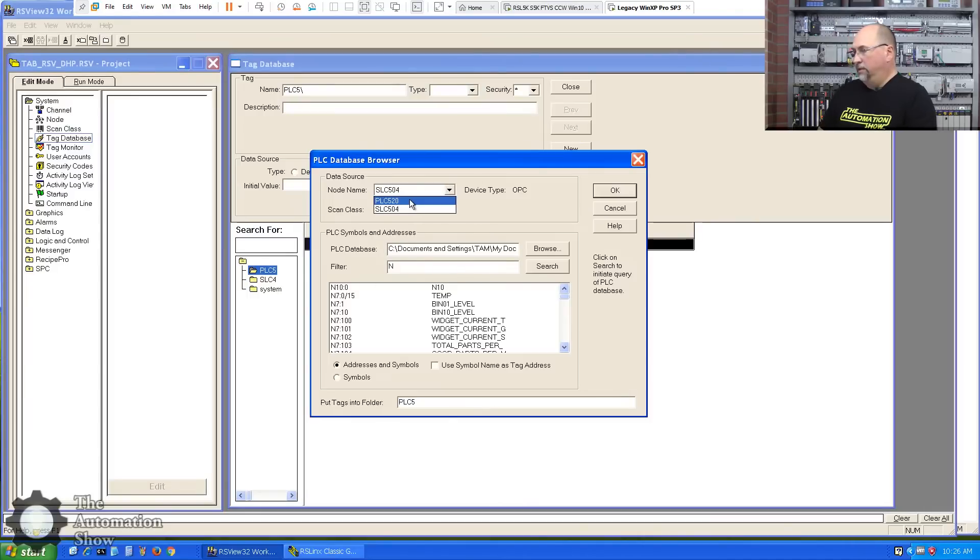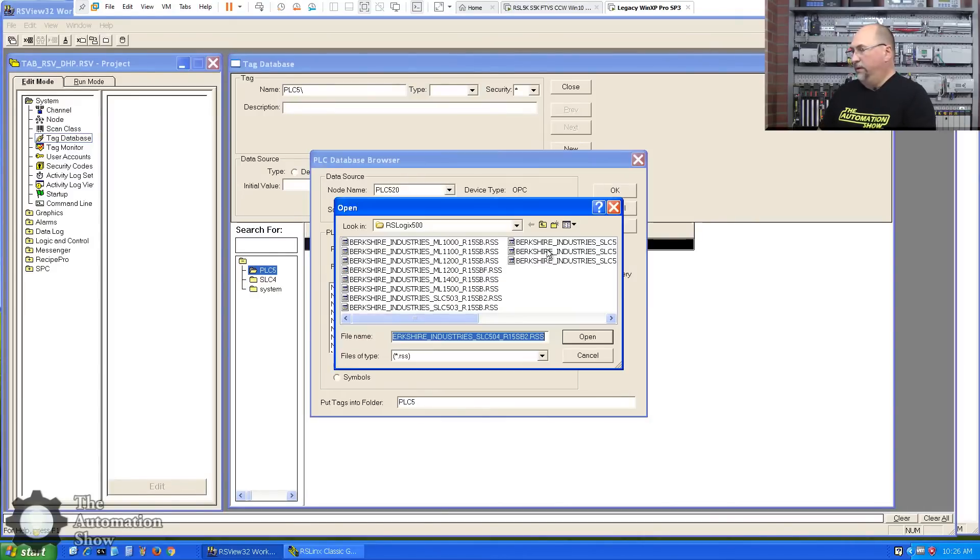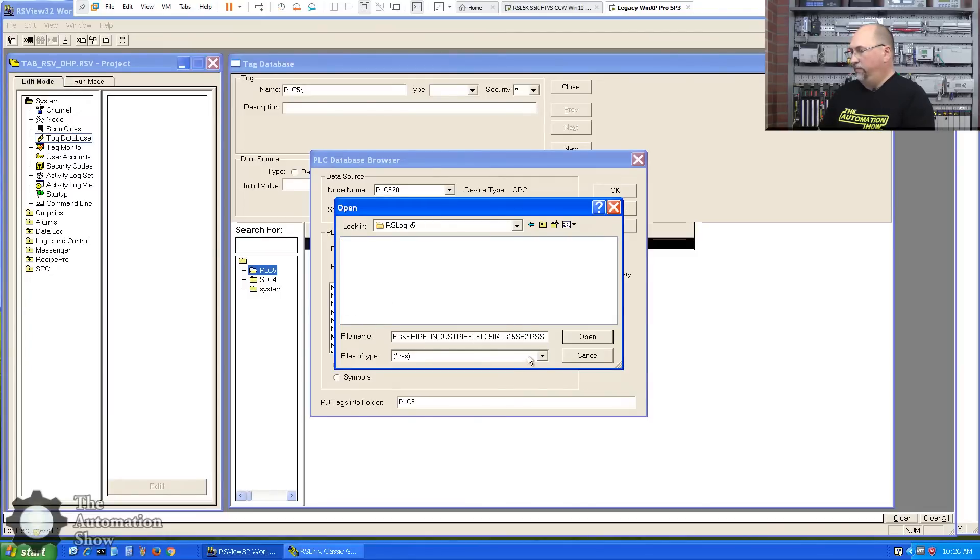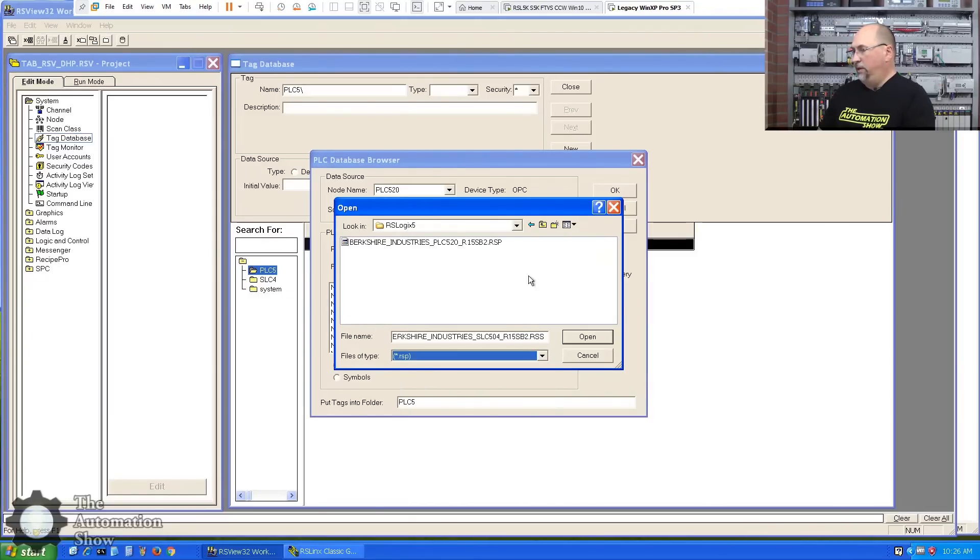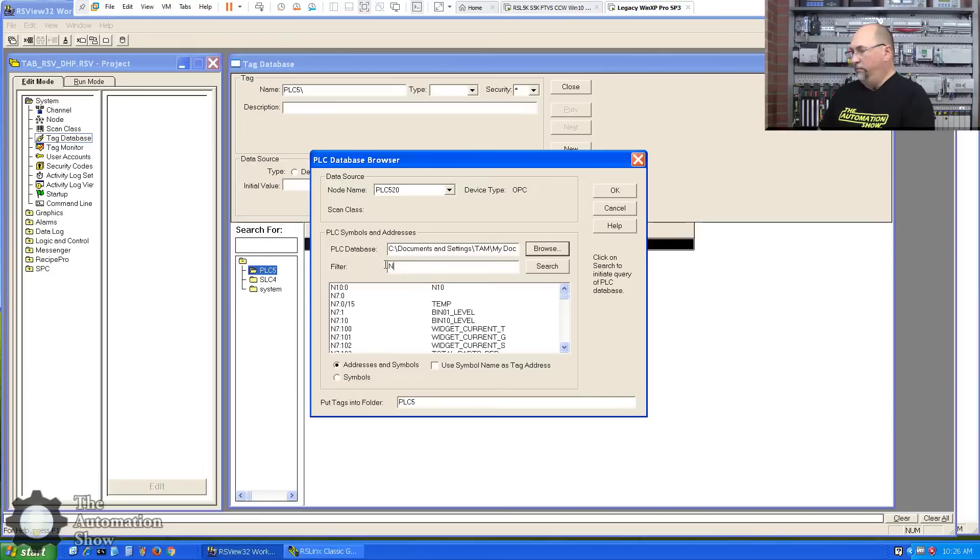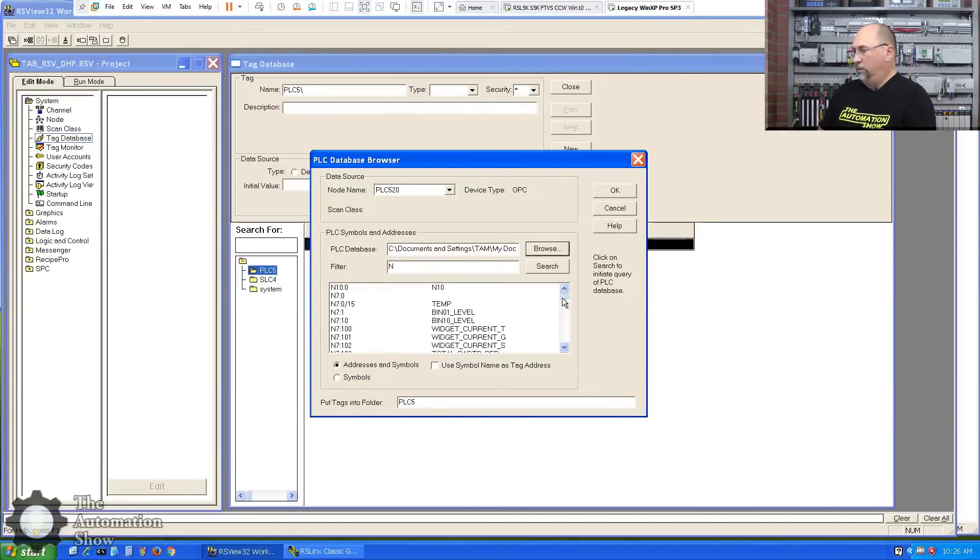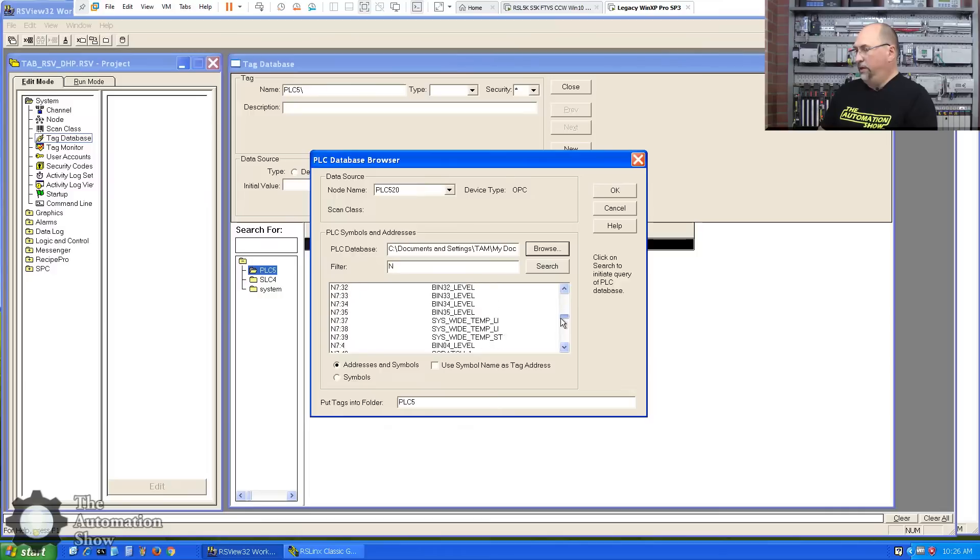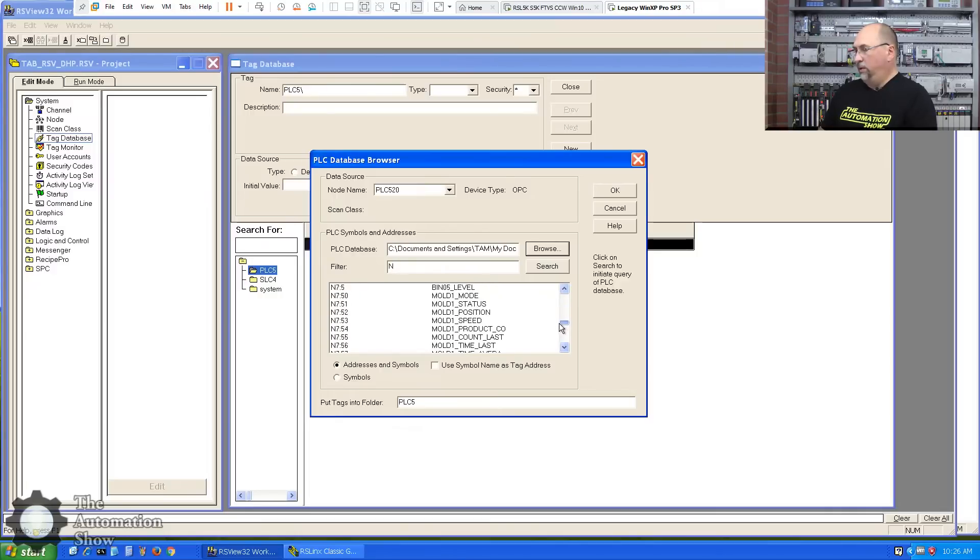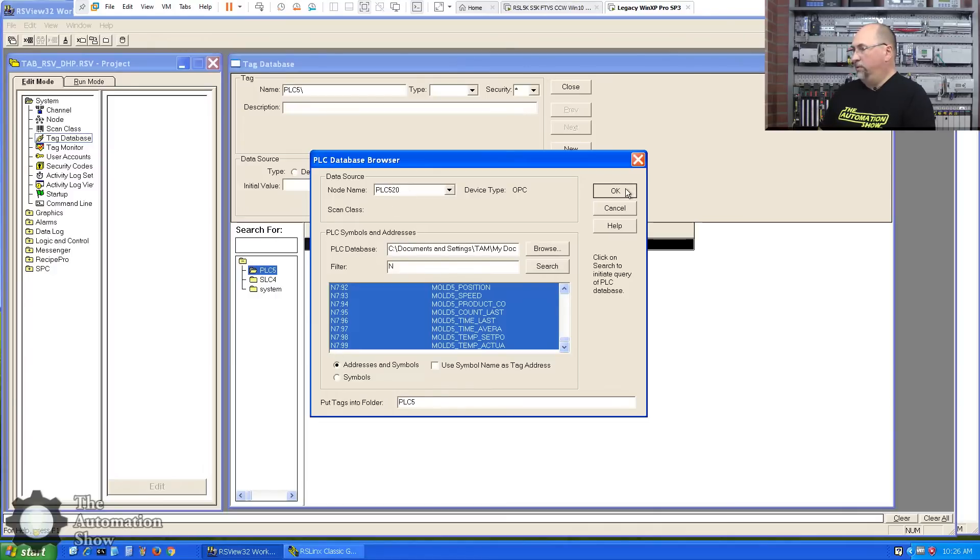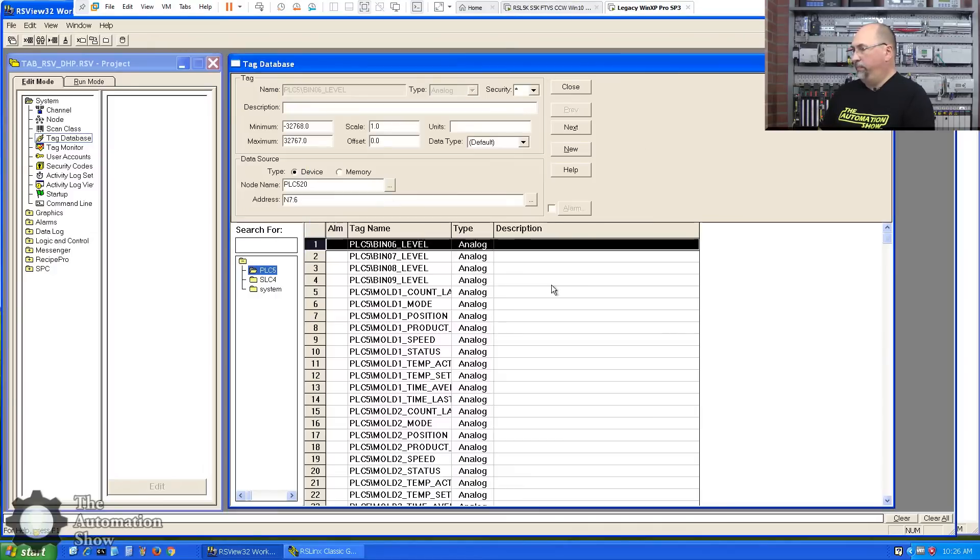And now I'm going to import the tags from my RSLogix files. So let me select the database browser. And let's see, the node is PLC520. The program is under, let's see, RSLogix 5. Change the type to RSP. There it is. I want to filter by integers. And I want N750 through 99. Those are my molding tags. Okay, everything looks good. Okay, let's go ahead and bring those in. Excellent.